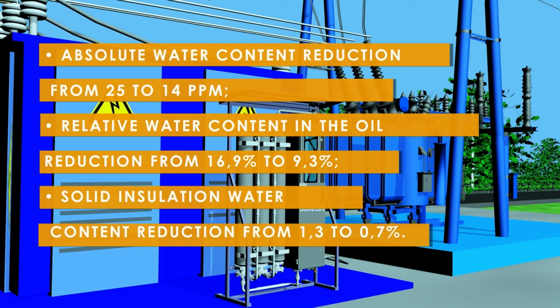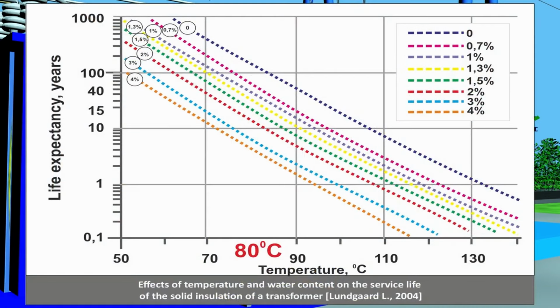Looking at the graphs that show influence of temperature and water content on the lifespan of solid insulation, we can see that, for example, reducing solid insulation water content from 1.3 to 0.7% at a temperature of 80 degrees Celsius extends the transformer lifespan by approximately 25 years.